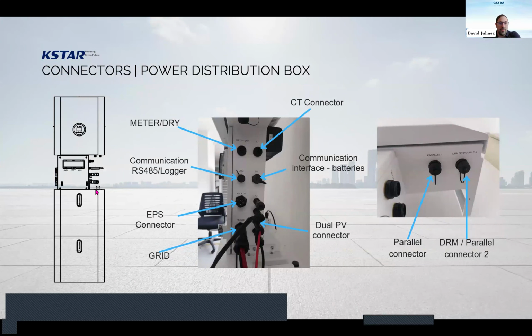Regarding the connection, this is the right side of the distribution box under the inverter. It has a separate meter connection terminal, the communication for the data logger stick, the backup load connection, and the AC grid connection. And it has a special CT connector if we want to use the CT, with a maximum of 20 meters between the inverter and the connection point of the grid. We can also use the CT connector to connect the CTs directly if we don't want the power factor value to be shown, or for grid analysis of the system.